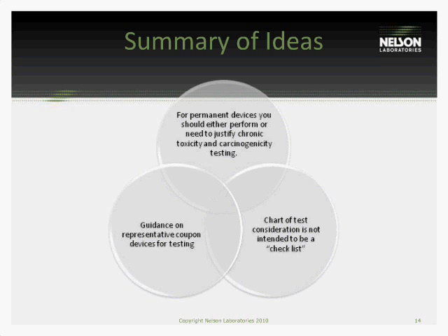The intent is to show you what categories are of concern for a contact or duration of a device. And then you have to scientifically look at those and justify which ones need to be done for your device. And that's what this guidance document now incorporates also: this chart they give you is not a checkbox, but is a way for you to evaluate what testing is needed for certain devices.